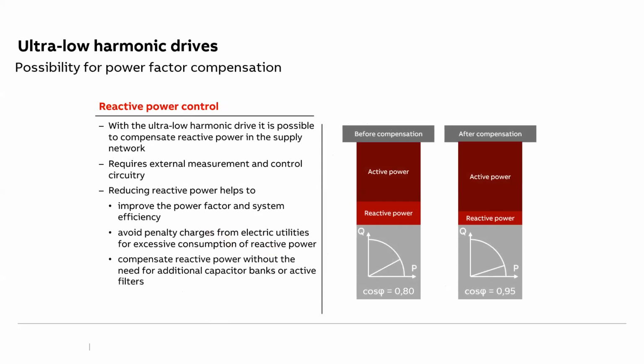Now, typically, when we receive the power, it is basically active and reactive power. So cos phi affects the power factor, basically. Here we see with this compensation, this active control, we can increase the active power, which is the actual useful power, and the reactive power, which is not useful power, is reduced, and we can achieve a higher cos phi by using this solution. So the penalty charges and the regulatory compliance, all those things are taken care of.